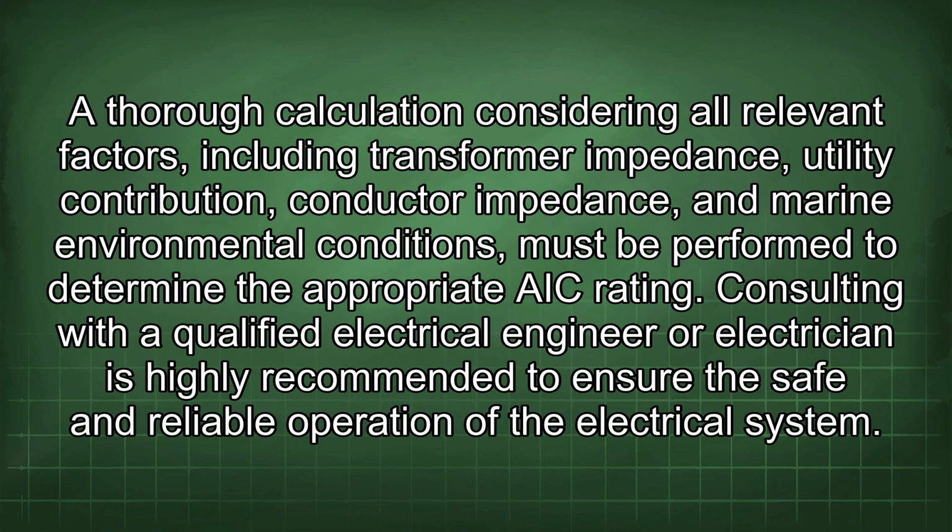A thorough calculation considering all relevant factors, including transformer impedance, utility contribution, conductor impedance, and marine environmental conditions, must be performed to determine the appropriate AIC rating. Consulting with a qualified electrical engineer or electrician is highly recommended to ensure the safe and reliable operation of the electrical system.